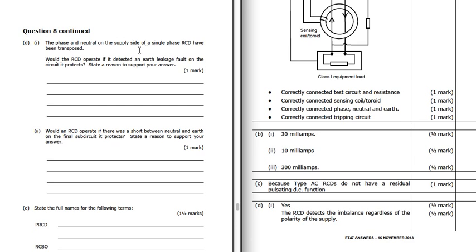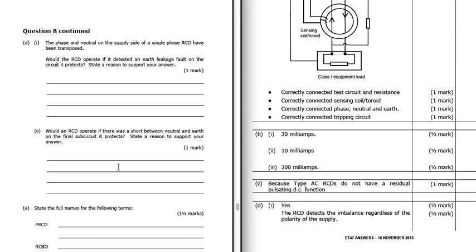The phase and neutral on the supply side of a single phase RCD have been transposed. So is this going to affect the operation? Well, the RCD isn't going to care. Is it going to operate? Yes. The RCD detects the imbalance regardless of the polarity of the supply. So it doesn't care which way around the phase and neutral are. If there's an imbalance there, it will operate.